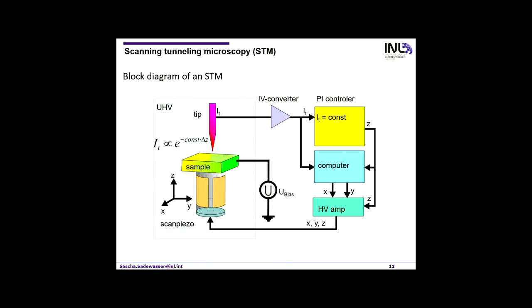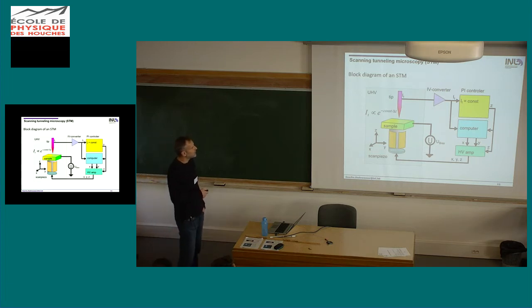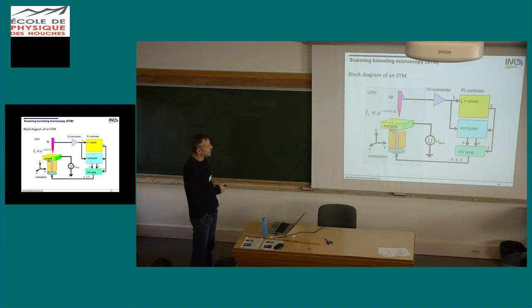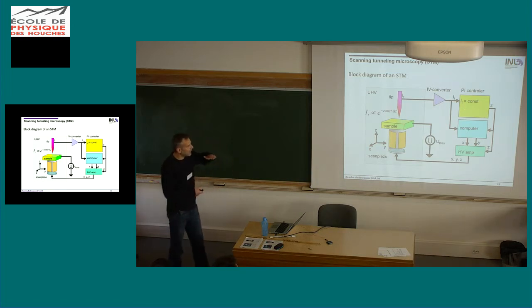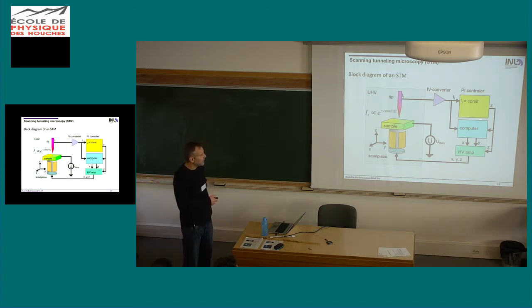So how is it built? This is a typical block diagram, very simplified, of a scanning tunneling microscope. We have the tip, of course, we have the sample. Then we need to scan the sample very precisely. So for this we use a piezo scanner, and I will explain all of these elements in the following slides. Then what we need is a current voltage converter, to look at the current that comes from between sample and tip. We have a controller that controls this current to be constant, and that at the same time gives our tip height signal, which we feed into a high voltage amplifier to apply to the piezos. And on the other hand, we have a computer that records all our signals and controls the scanning.